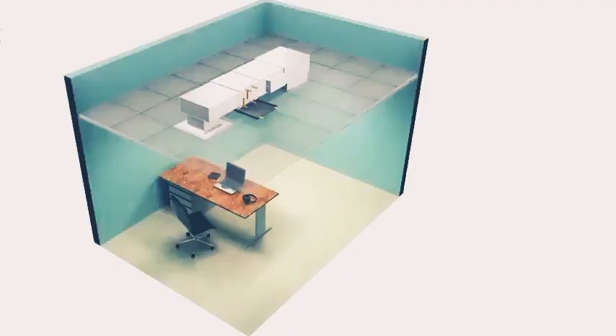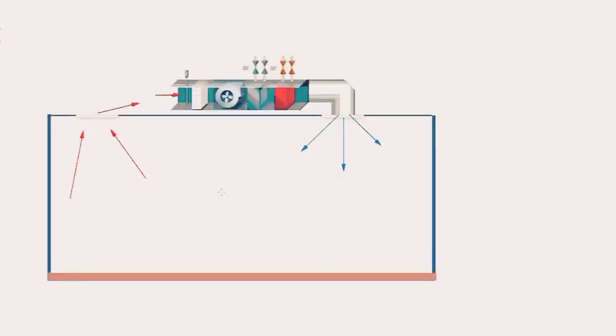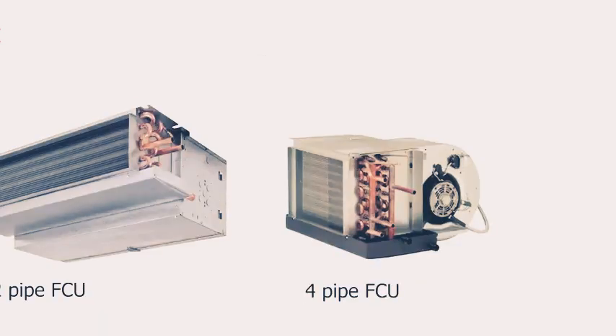The return air grill and supply air diffuser, typically set flush into the ceiling, will be ducted to and from the fan coil unit and thus allow a great degree of flexibility for locating the grills to suit the ceiling layout and/or the partition layout within a space. It is quite common for the return air not to be ducted, and to use the ceiling void as a return air plenum. Fan coil units are divided into two types, 2-pipe fan coil units or 4-pipe fan coil units.